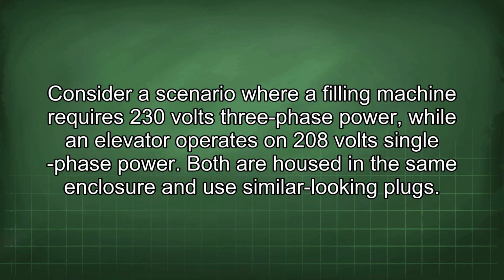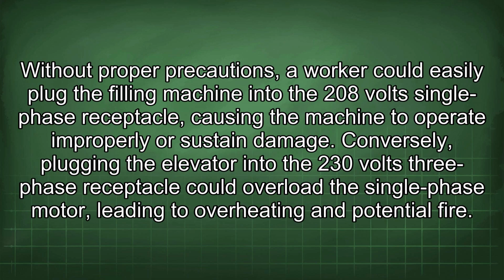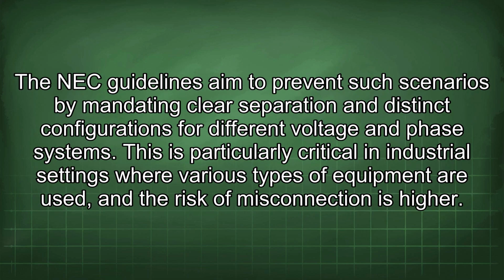Consider a scenario where a filling machine requires 230 volts three-phase power, while an elevator operates on 208 volts single-phase power. Both are housed in the same enclosure and use similar-looking plugs. Without proper precautions, a worker could easily plug the filling machine into the 208-volt single-phase receptacle, causing the machine to operate improperly or sustain damage. Conversely, plugging the elevator into the 230-volt three-phase receptacle could overload the single-phase motor, leading to overheating and potential fire. The NEC guidelines aim to prevent such scenarios by mandating clear separation and distinct configurations for different voltage and phase systems. This is particularly critical in industrial settings where various types of equipment are used, and the risk of misconnection is higher.